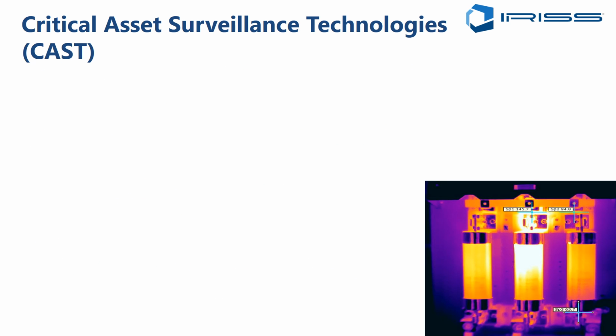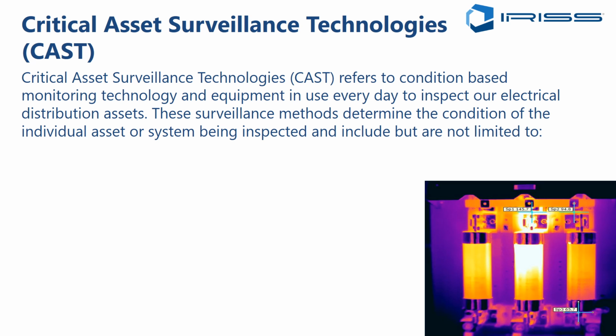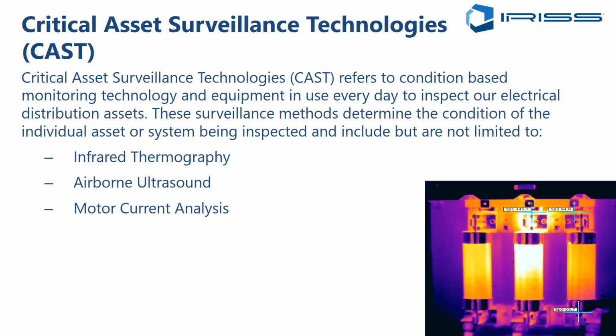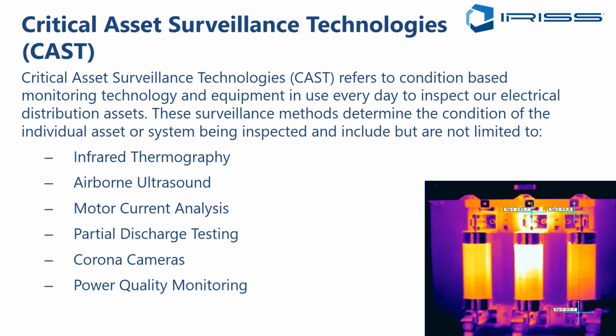So when we look at critical asset surveillance technologies, or what we call CAST, basically this refers to monitoring technology or equipment that's in use every day on our electrical distribution assets. These surveillance methods determine the condition of the equipment that we're looking at, and the tools we're using are infrared thermography, airborne ultrasound, motor current analysis, partial discharge testing or corona cameras, power quality monitoring, and visual inspections. These are all part of what we have to do on a routine basis on our electrical equipment. A daily basis would be great, but there are a lot of hurdles involved with doing that.